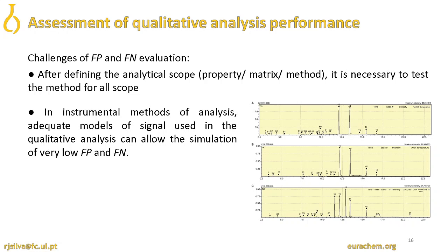An alternative to this strategy, applicable to cases where you have instrumental methods of analysis and a quantitative criterion for the identification, is developing models of the performance of your instrument, and simulating the chance of an item without the analyte producing by chance a signal above the threshold for the identification. And this is very useful if you have extremely selective identification, just like GC-MS/MS.